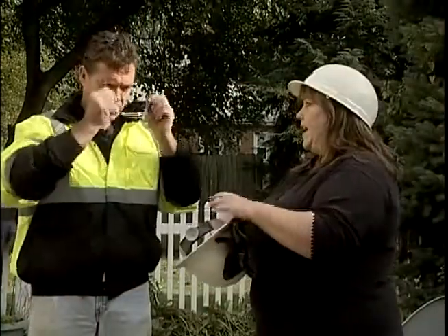Builders and contractors must do a number of things to protect their employees from electrical hazards and electrocution. If work is being done around overhead power lines, the employer must see that the lines are de-energized and grounded by the owner or operator of the lines, if at all possible.